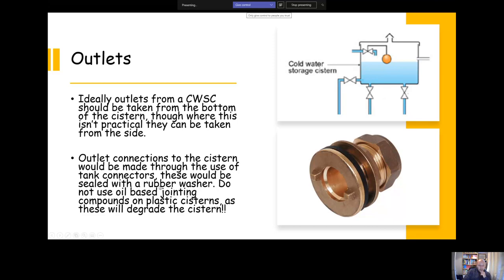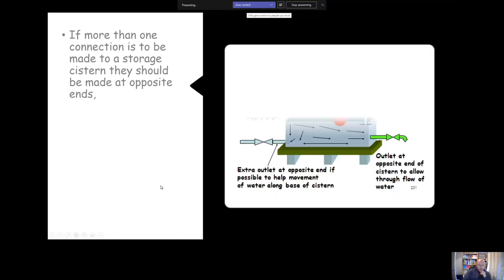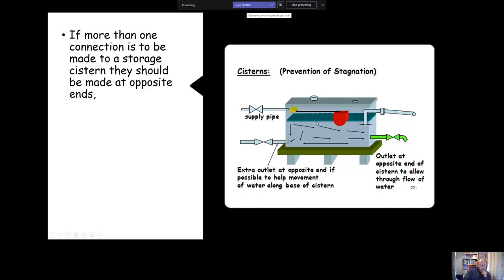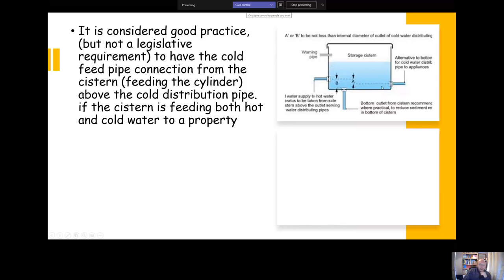If we have more than one connection, we should make them at opposite ends. That's to encourage through flow of water and minimize the risk of stagnation. Ideally we should always take our cold feed connection, the one which is feeding the hot water cylinder, off above our cold distribution. That's essentially to help prevent scalding.